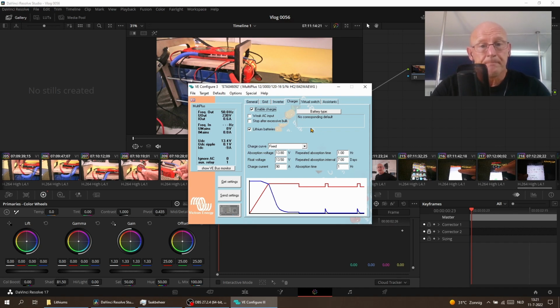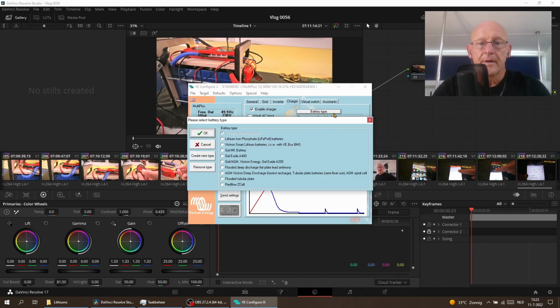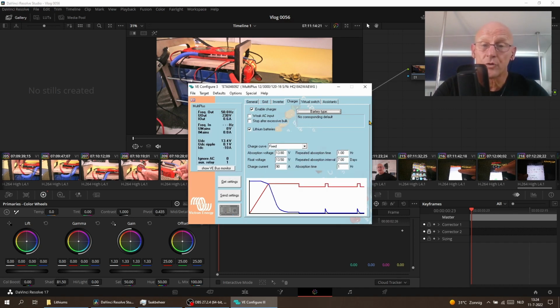Battery type - since we installed lithium iron phosphate batteries, it would seem logical to select this. But when you do, you get an absorption voltage of around 14.4, which is too high, because lithium batteries don't like being fully charged, so we want to avoid that.